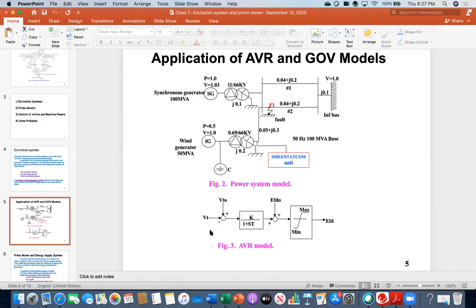During a fault condition, what will happen? Because there will be a difference in voltage, some amount will be added so that you can increase the excitation. That will be your field voltage, and if you increase the field voltage, you are increasing the excitation. You all know the two main governing factors behind producing the voltage. One is the flux, or the DC field; the other is the speed. The speed comes from the prime mover, and the excitation, or flux, comes from the DC field circuit. That is the function of the AVR.